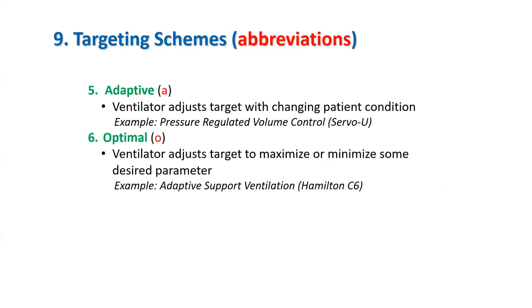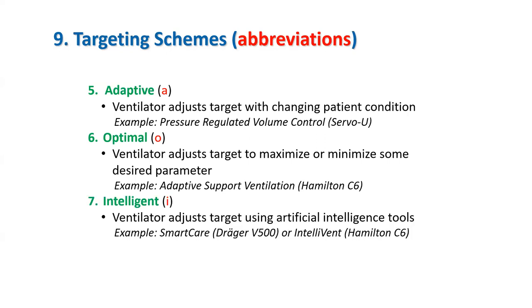Optimal targeting means that the ventilator uses adaptive targeting to select both an inspiratory pressure and frequency for mandatory breaths that minimizes the power transfer from the ventilator to the respiratory system. Optimal targeting is, in fact, the way the brain controls the ventilatory pattern to minimize caloric expenditure during normal breathing. Recent research suggests that minimizing power transfer may decrease the risk of ventilator-induced lung injury.